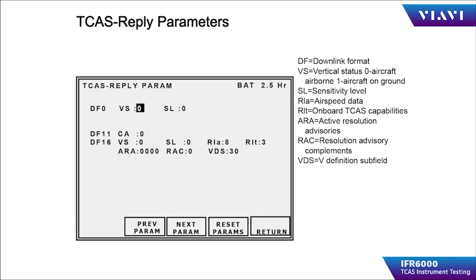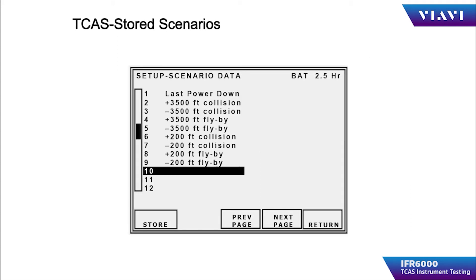The TCAS reply parameters page affords the operator the opportunity to set some of the reply parameters related to the acquisition and operational status of the target being generated. Some of these parameters are vertical status, capabilities, sensitivity levels, etc. The operator can choose to configure the parameters of the target manually or can select from one of the canned scenarios provided with the IFR 6000. There are three empty scenario slots to allow the operator to save and subsequently recall a custom setup.